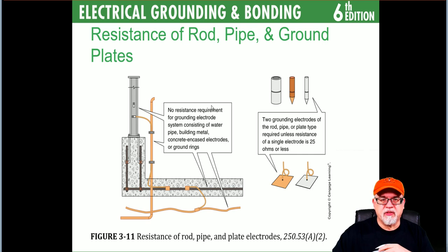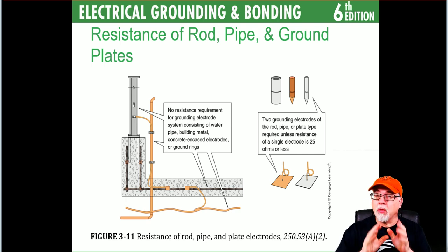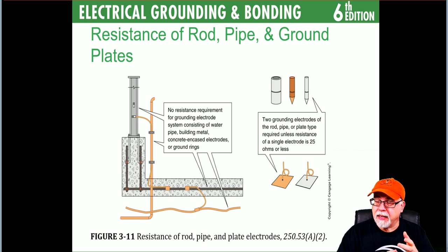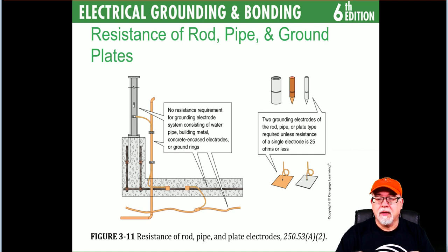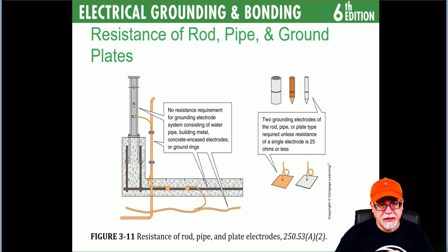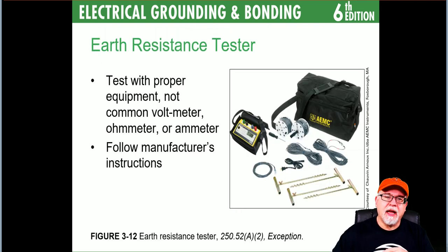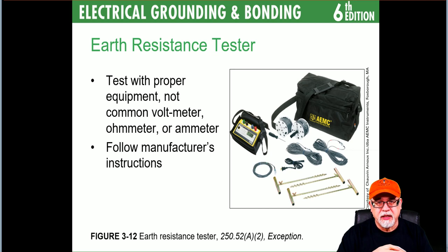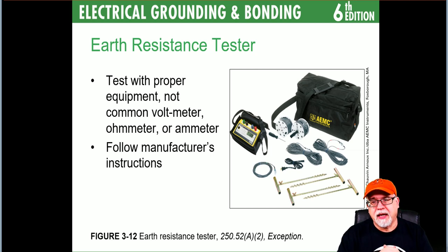The resistance requirement of 25 ohms or less only applies to rods, pipes, and plates — not to other electrode types. Anywhere else the actual resistance could be a thousand ohms and it doesn't require any supplement. Testing requires earth resistance testers; the three-point fall-of-potential method requires enough space on the property because it's all about the spacing of the test probes.